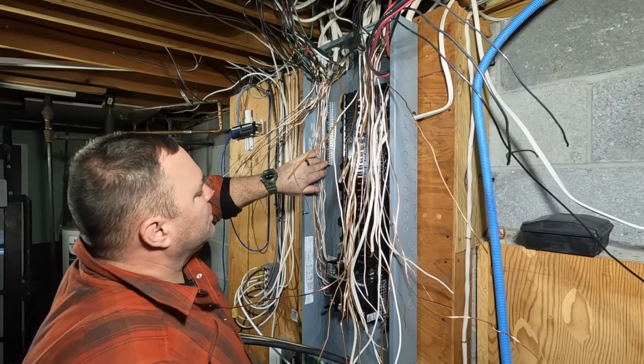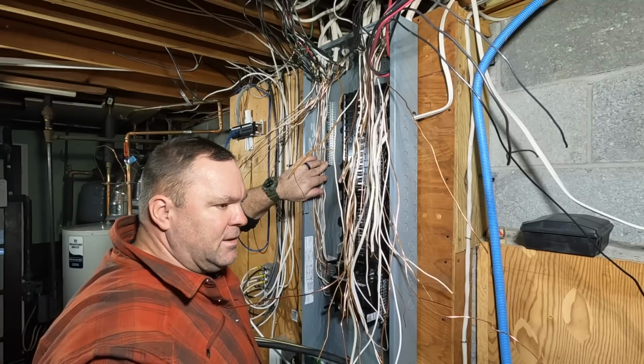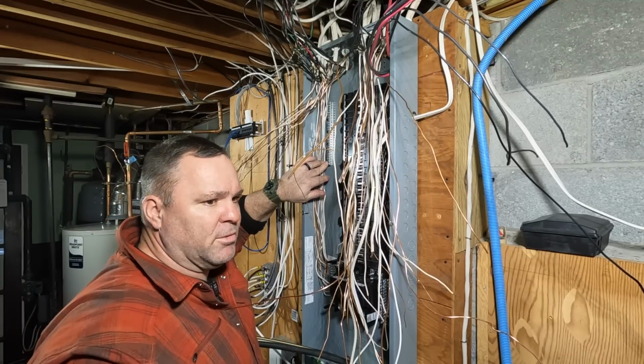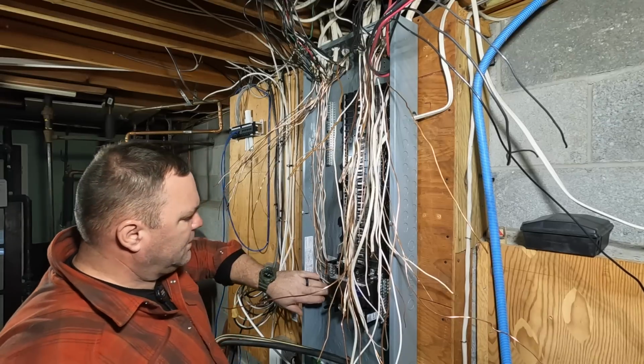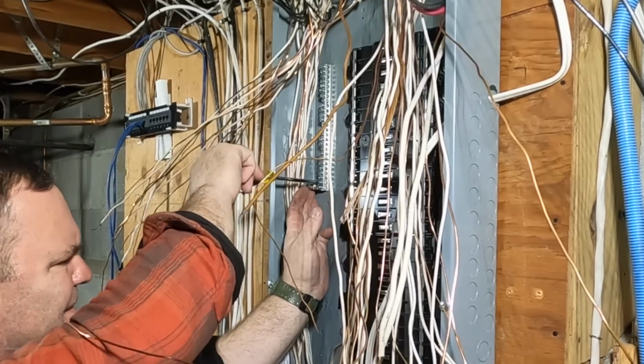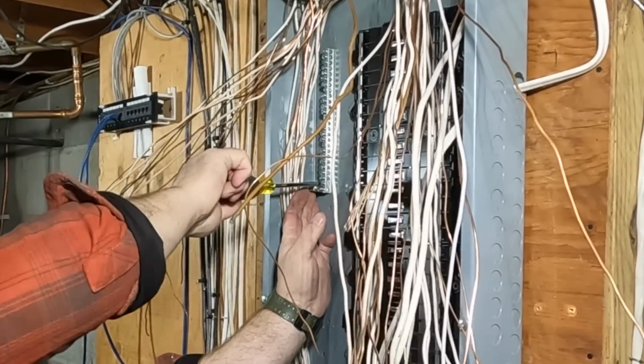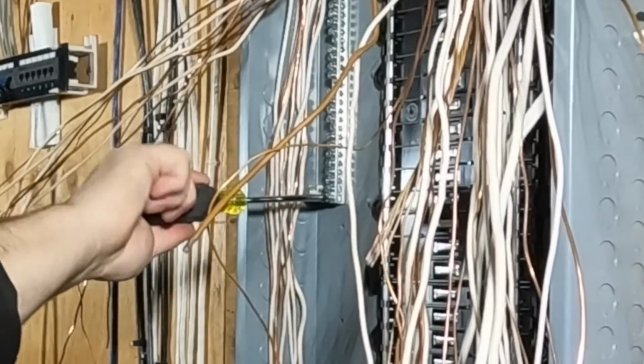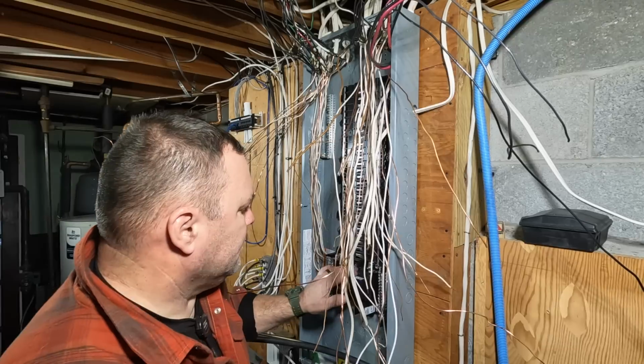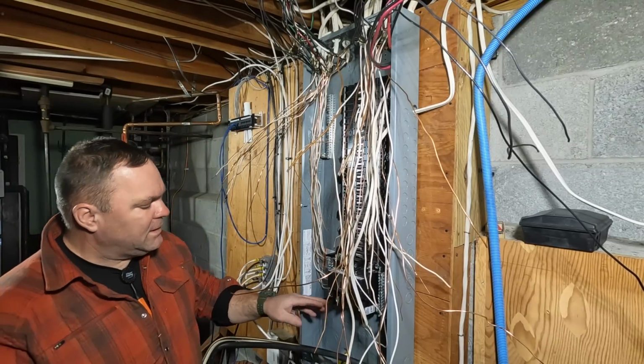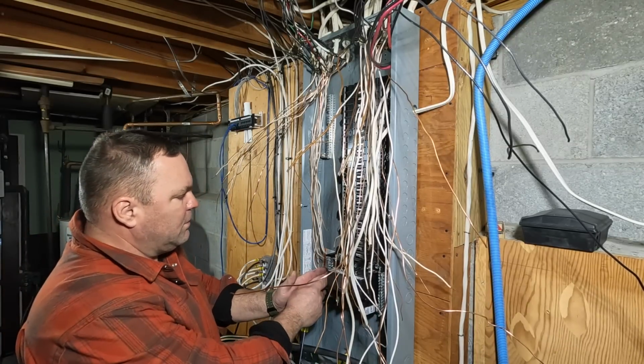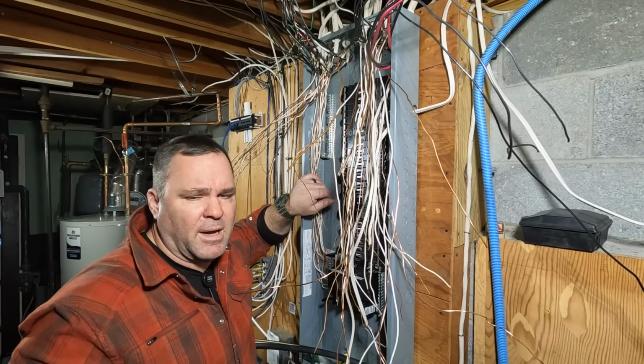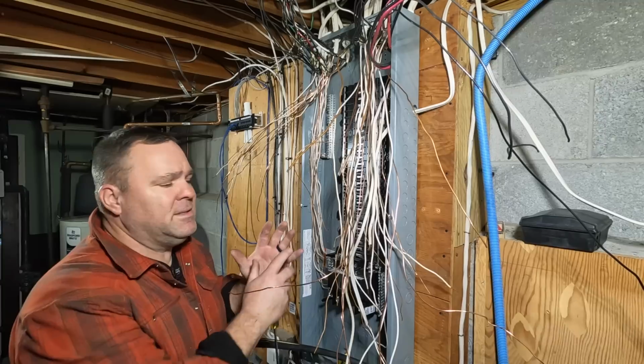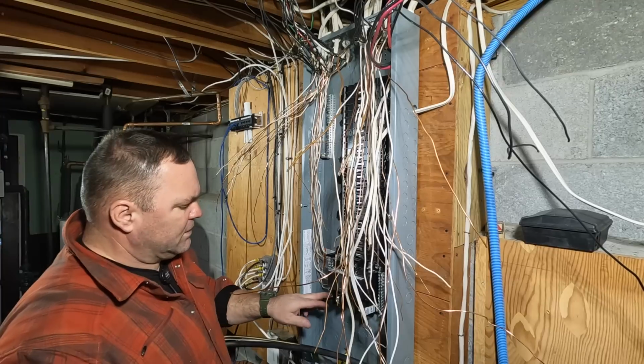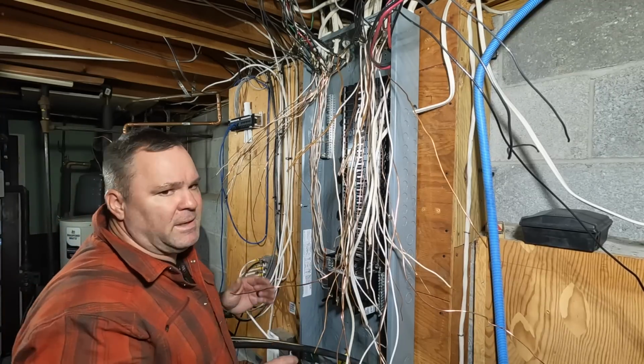So what we need to do is just have a jumper. I believe it's number 6. I'm going to check. If it's not 6, it's definitely number 2 aluminum or number 4 copper, and we're just going to jump from here down to here and call it a day. And the jumper that we're going to put in is going to go from this lug down to the terminal that came with the panel, the official neutral bar. And the neutral bar, when you put the bonding jumper in and the bonding screw, it bridges the neutral terminal to the enclosure. That's what grounding and bonding is all about. We bring all of our grounding and bonding to the main disconnect, which is my main breaker right here, and we insert this main bonding jumper screw only here at the main disconnect.